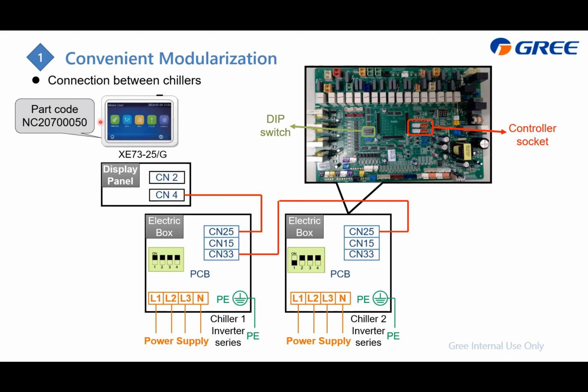From here, there are just two ports. CN4 is for connecting to the chiller, which is the outdoor unit's control main board. And here is the controller socket, which is this CN25 and CN33. Besides, you also need to change this switch, which is located here.